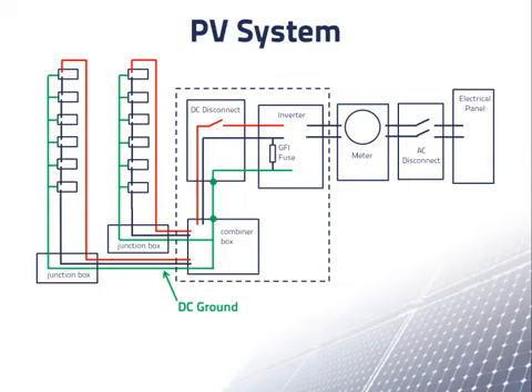On the AC side of the system, the equipment grounding conductor goes from the inverter through the other components into the electrical panel. Since the enclosures of the inverter and the other components are almost always metal, these enclosures also need a connection to the equipment grounding conductor. The equipment grounding conductor is connected to a grounding bus in the electrical panel, and the bus is connected to a grounding rod. The equipment grounding conductor on the AC side of the PV system is called the AC ground.